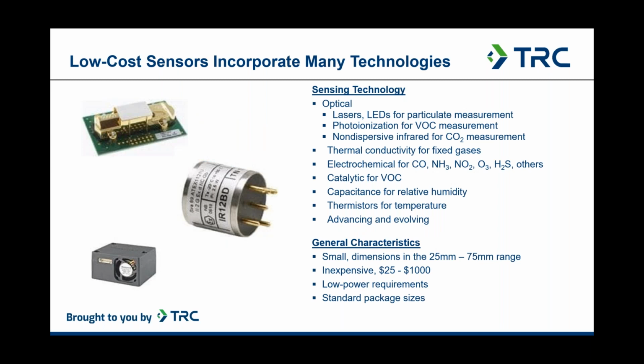Low-cost sensors incorporate a range of different technologies, and what we very commonly see is optical technology. Lasers are very important for particulate measurement. Photoionization is important for VOC measurement, and NDIR is important for CO2 measurement. Catalytic procedures are also used for VOC measurement, and in some of the comfort parameters, relative humidity is measured by capacitance and temperature is measured by thermistors. But this is a rapidly advancing and evolving area where new sensors are being developed all the time, and the existing sensors are constantly being improved.